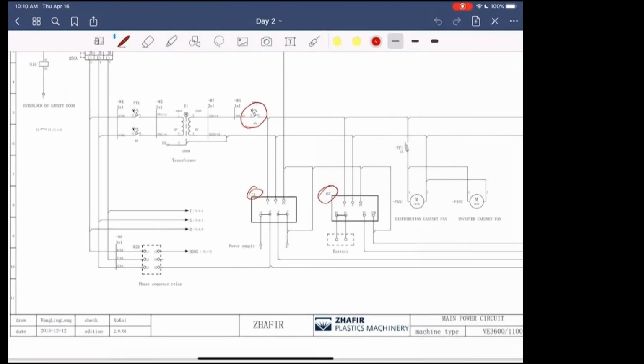Keep in mind something that people aren't aware of: if you follow this line, it's still 220 volts. It's going to your power supply, which I already showed, but that's not what I want to show you. It goes here to all your cabinet fans. So all your cabinet fans are 220 volts, not 24 volts. Again, be careful when you're opening the cabinets. If the fans are running, don't touch any of the terminals or the little connectors on the fans, because that is 220 volts. It is protected by a 2 amp fuse, but by the time the 2 amp fuse kicks out, I'm sure you'll feel the 220 volts.